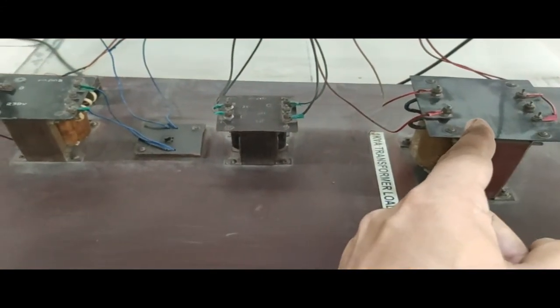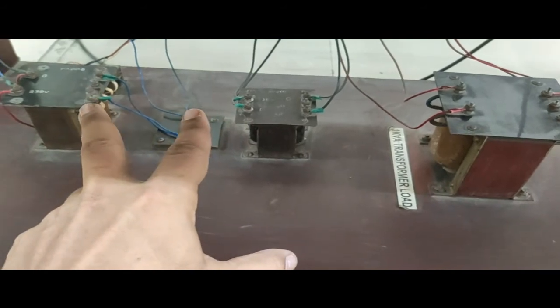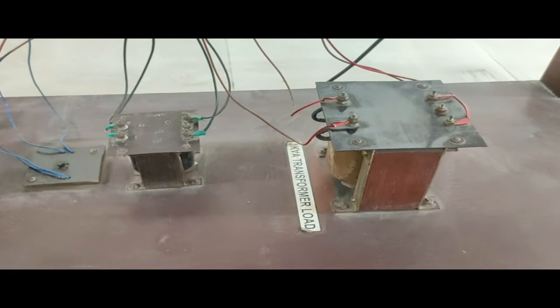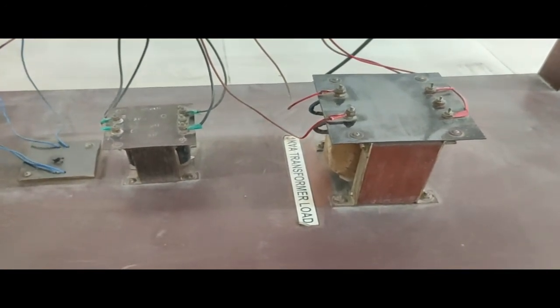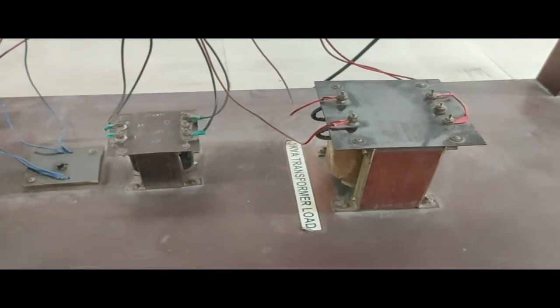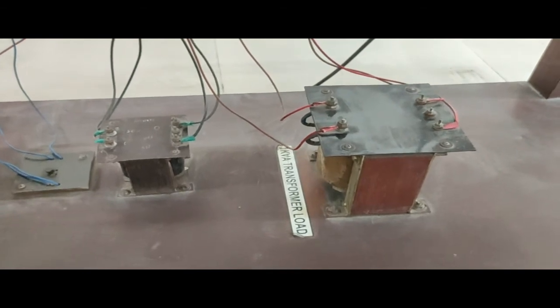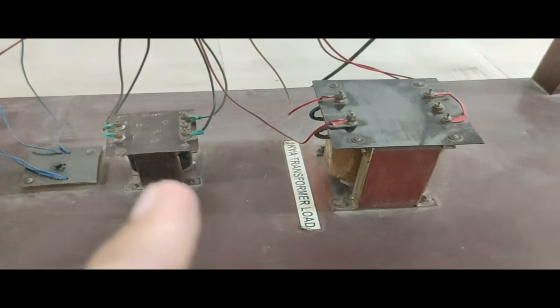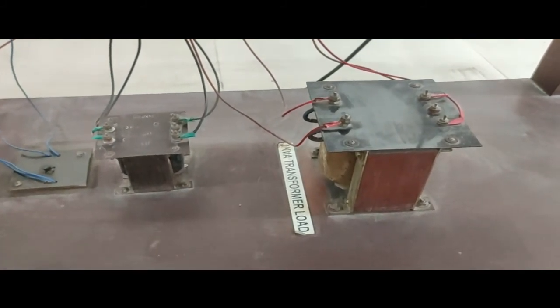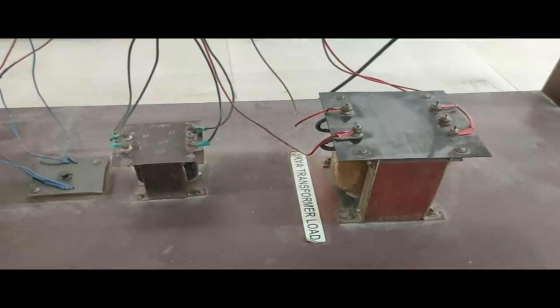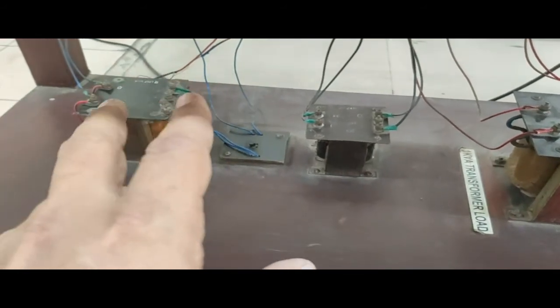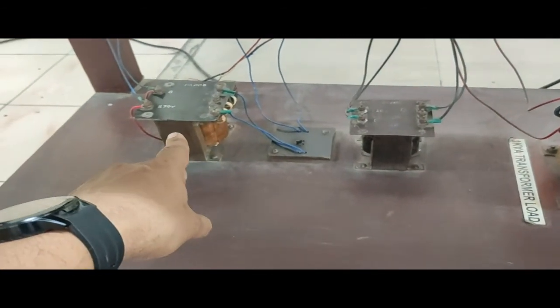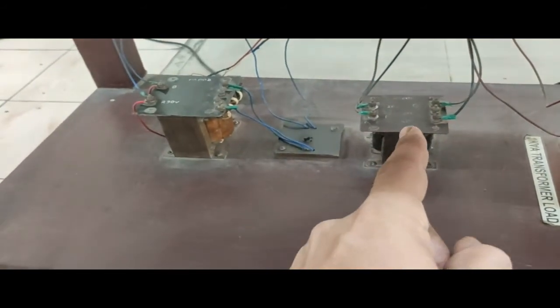Now coming to the down position, here you see 3 transformers, transformer number 1, 2 and 3. These 2 transformers are required for the under voltage relay, and this one is only required for the earth fault relay. Using the short circuit transformer we can give the fault current, because here we simulate the fault. That means we need to increase the amount of current required by the relay. How do we increase the current? There is a short circuit transformer, and using it we can increase the current as if a fault is there which is sensed by the relay. So this transformer is used as a load, and those 2 transformers are for the under voltage relay, because in the under voltage relay 30 volt DC is required for one of the coils, and 110 volt AC is also required. This one is for converting the AC to 30 volt DC, and that one is for converting the 230 volt AC to 110 volt AC, which is required by the under voltage relay.